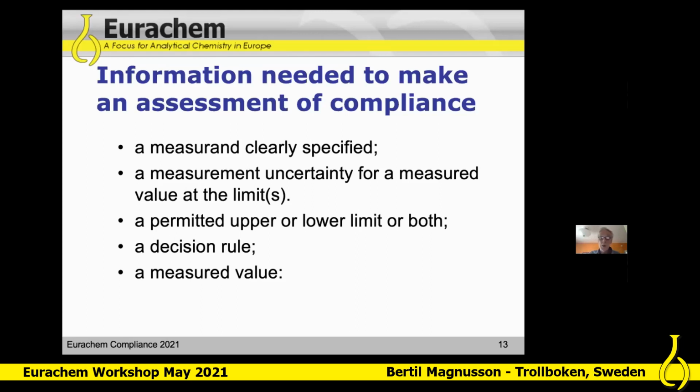We will need a decision rule, and in this rule, we really want to have very high confidence that we get a nickel value within the spec. And of course, we will have a measured value. In this case, it was 16.1.